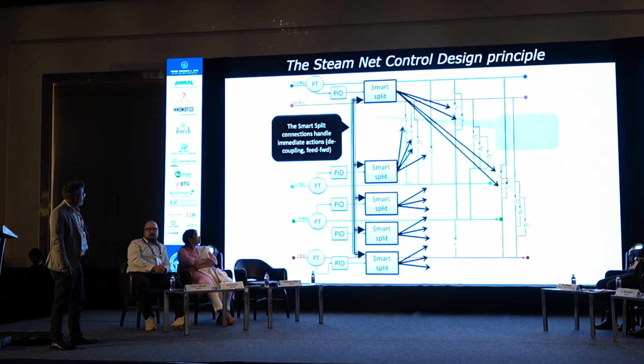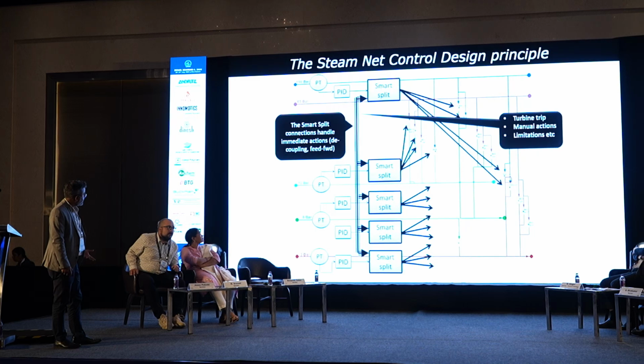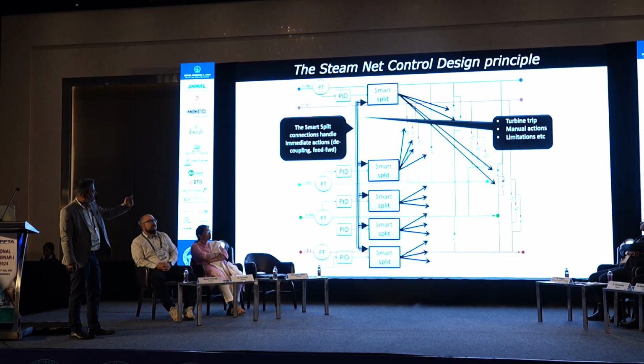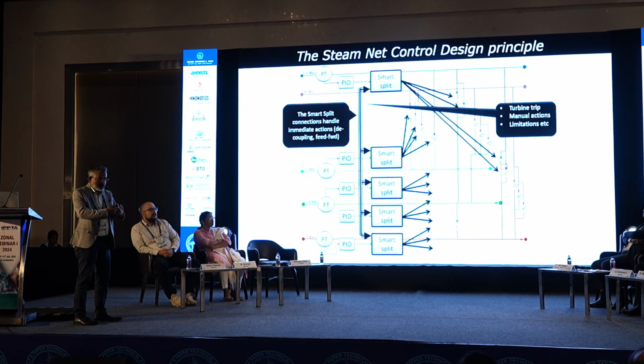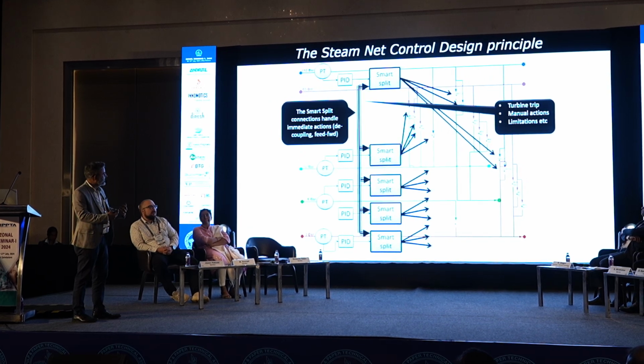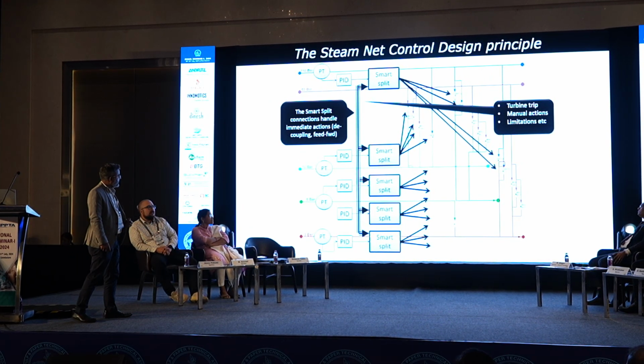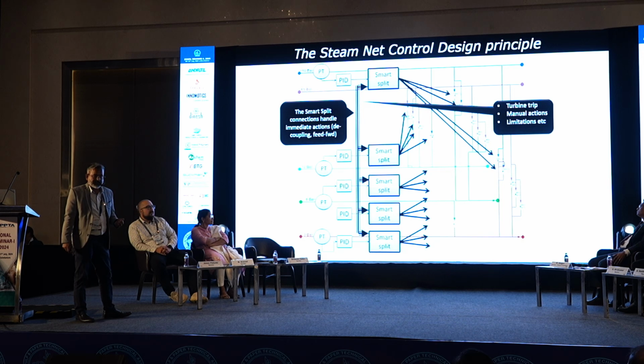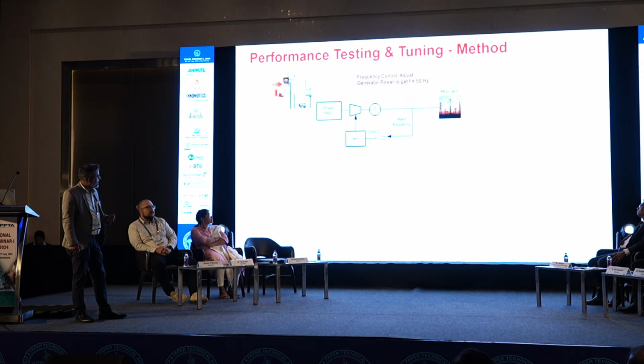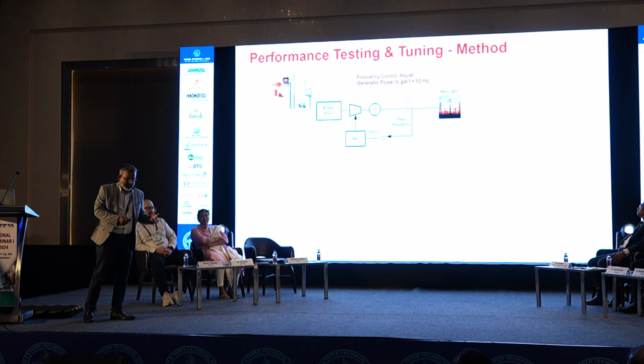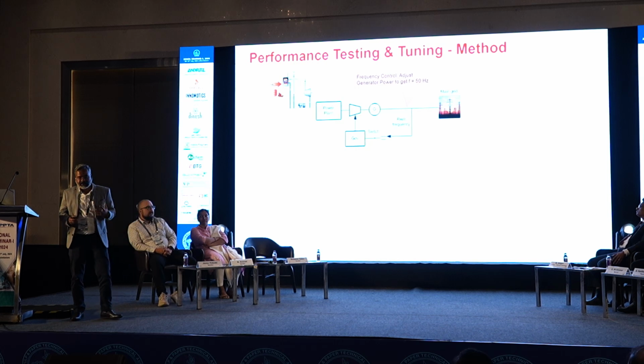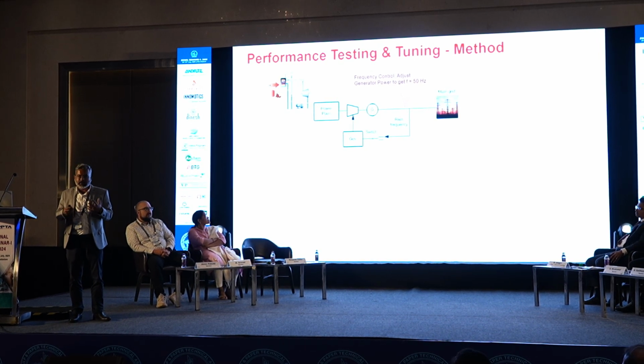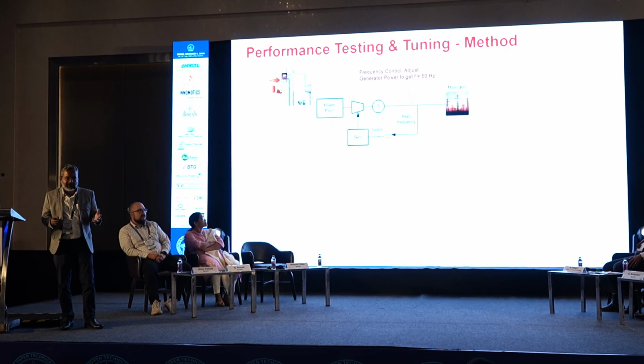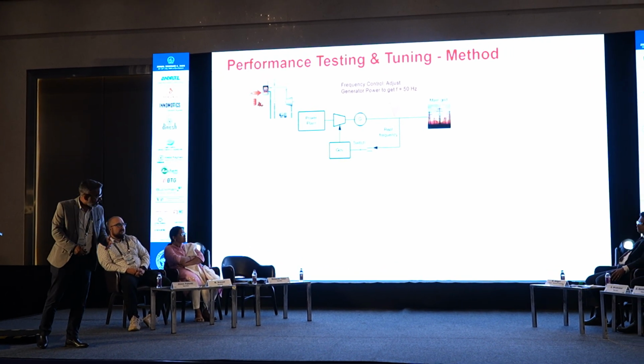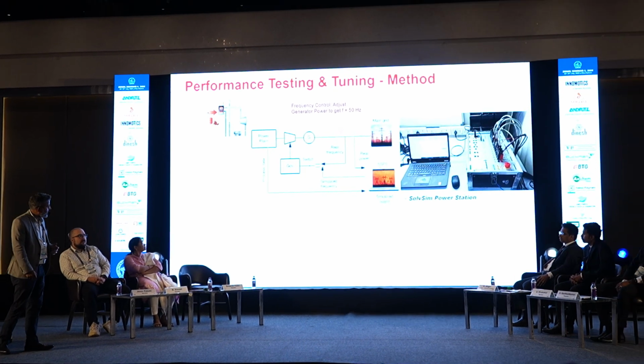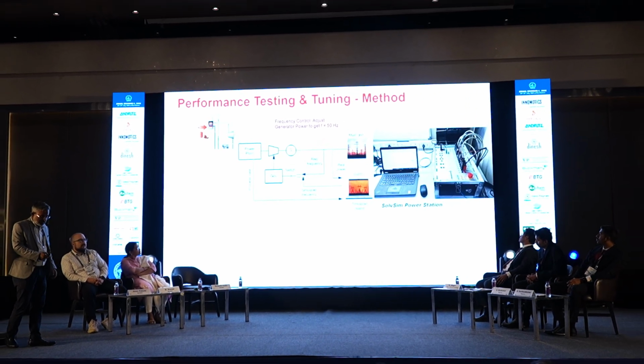So this is the smart split connections; they handle the immediate actions. Also, in the case when there is a turbine trip, this control system immediately decouples, and manual actions and limitations can then be taken care of. And once we did this study, we validated these simulation results with the actual test on site. That is where we have our testing kit through which we test this system and its performance.